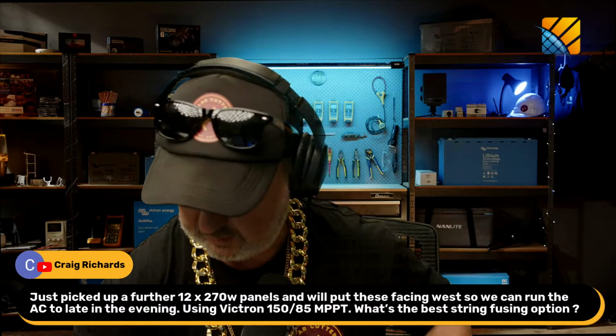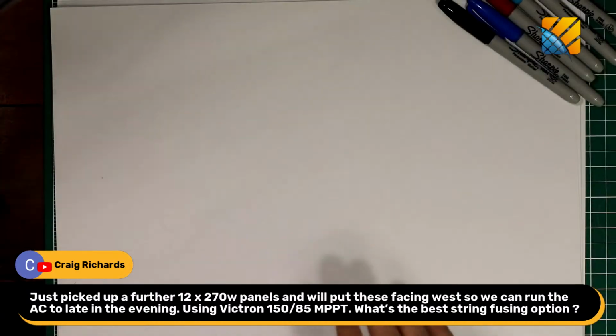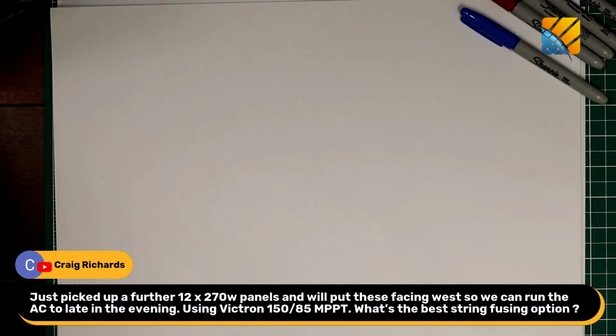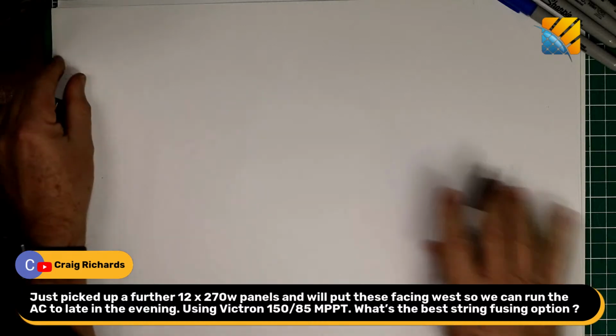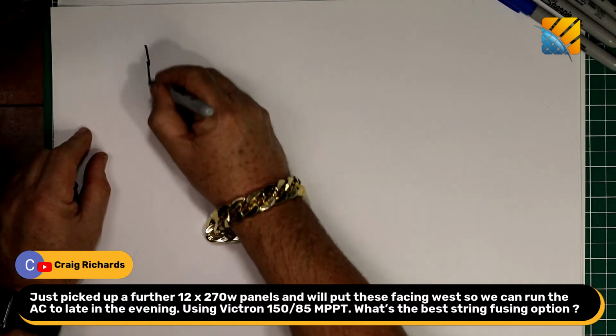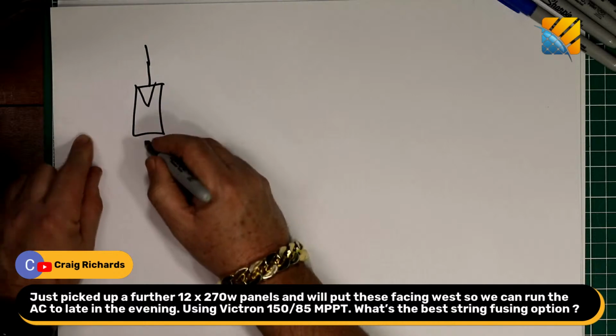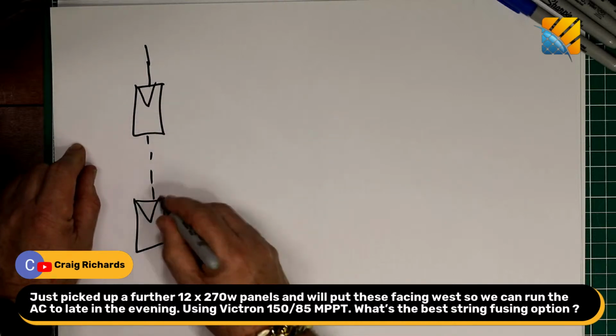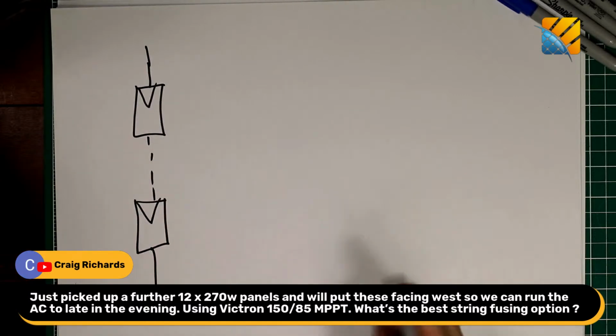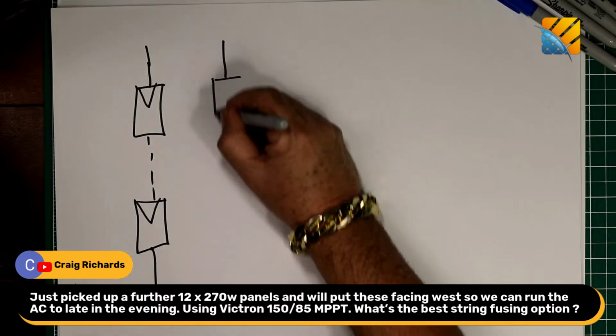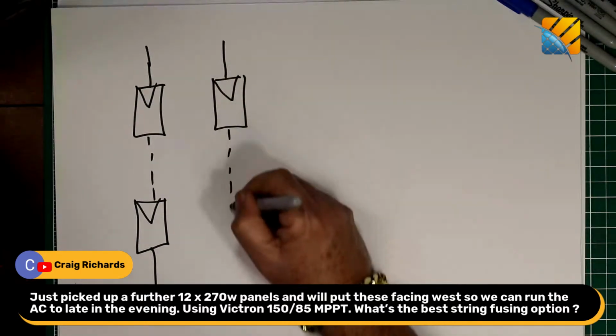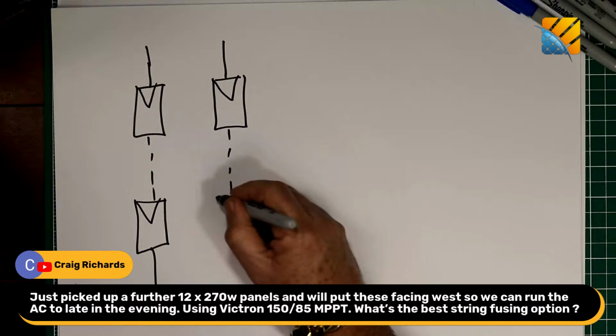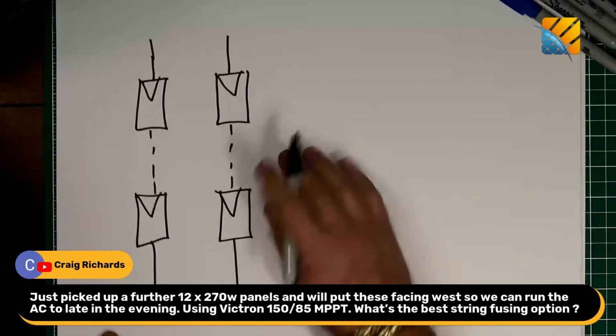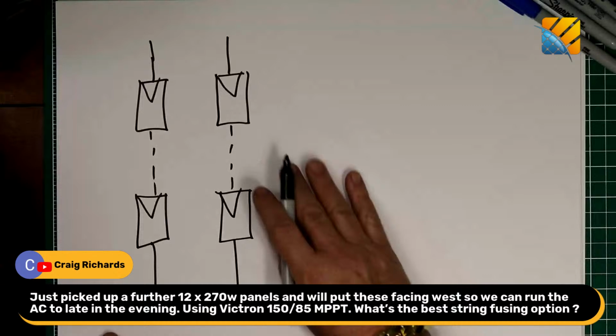Hang on. I do have a drawing. Wait a minute. I knew there was a reason for me setting up my drawing table here. Craig, a really simple explanation of string overcurrent protection is this: when you have multiple strings of panels, and a string is a series connection of panels, there's one string. When you've got multiples in parallel, under a fault condition one string can backfeed another. So there's a requirement to calculate the maximum reverse current that any one string can take.